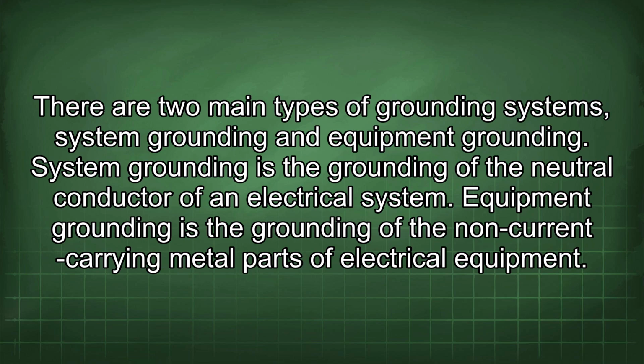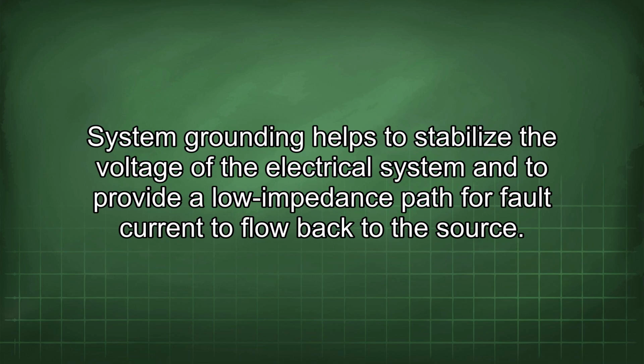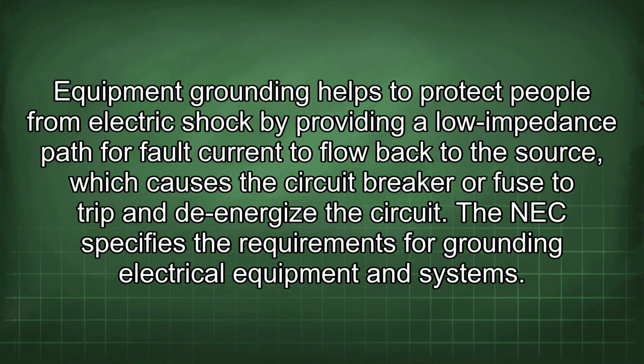System grounding is the grounding of the neutral conductor of an electrical system. Equipment grounding is the grounding of the non-current carrying metal parts of electrical equipment. System grounding helps to stabilize the voltage of the electrical system and to provide a low impedance path for fault current to flow back to the source. Equipment grounding helps to protect people from electric shock by providing a low impedance path for fault current to flow back to the source, which causes the circuit breaker or fuse to trip and de-energize the circuit.